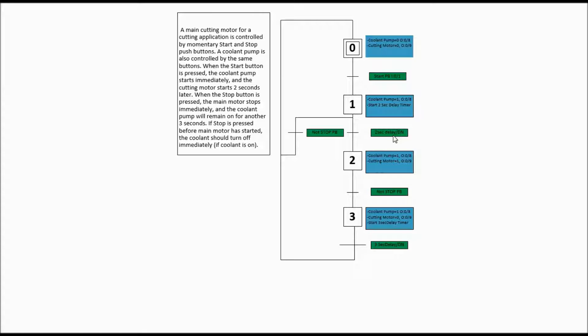If we wait until the 2-second delay is completed, we go on to step 2. Step 2 is coolant pump equals 1, and also the cutting motor equals 1 as well. We wait for our next transition, which is when the stop button is pressed. Once stop is pressed, we keep the coolant pump on, the cutting motor shuts off immediately, and we start a 3-second delay timer for the coolant pump. Once that 3-second delay is done, we return back to step 1.